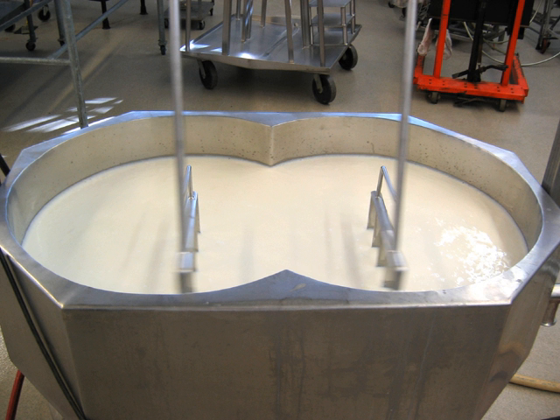The code also notes that the minimum pasteurization conditions are those having bactericidal effects equivalent to heating every particle of the milk to 72 degrees Celsius for 15 seconds (continuous flow pasteurization) or 63 degrees Celsius for 30 minutes (batch pasteurization), and that to ensure each particle is sufficiently heated, the milk flow in heat exchangers should be turbulent, i.e. the Reynolds number should be sufficiently high.